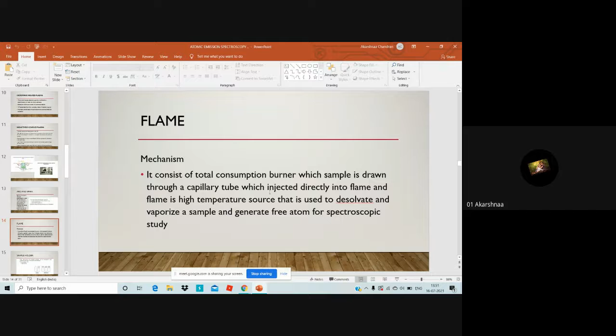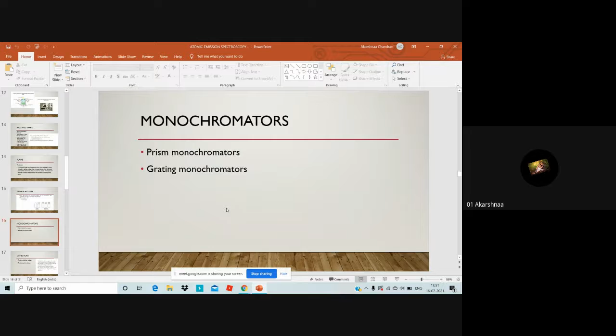And it consists of sample holders. It is of two types, solid samples and liquid samples. The function of the sample holder is to introduce the sample into the electrical discharge. Monochromators used are prism monochromators and grating monochromators. Detectors are photomultiplier tubes and photographic plates. For qualitative analysis, a photographic plate is used on which all the emission lines from the sample are recorded. This photograph of the emission spectrum helps in the measurement of the wavelength of radiation lines. From these lines, emitting elements can be identified.